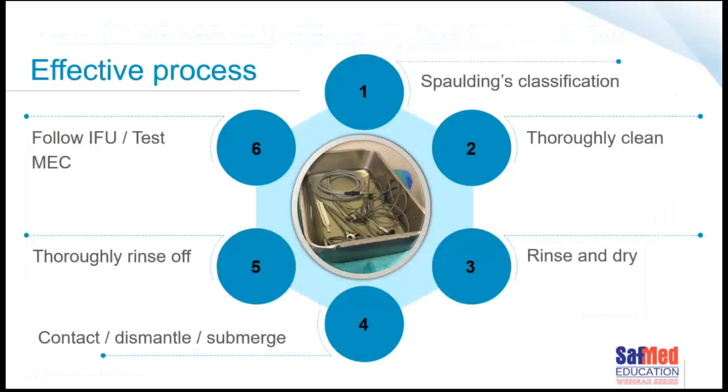Well, the first thing is, have we looked at the device and have we understood how we are going to use it? If it is a critical device that's going into a sterile part of the body, is going to make contact with blood, it needs to be sterilized, not high-level disinfected. And if you're using high-level disinfection to replace sterilization, why?